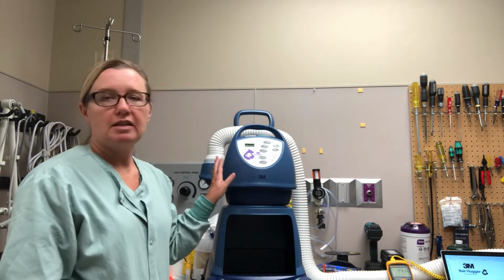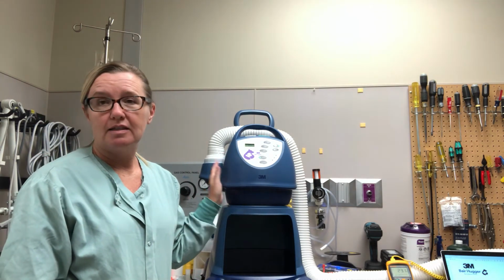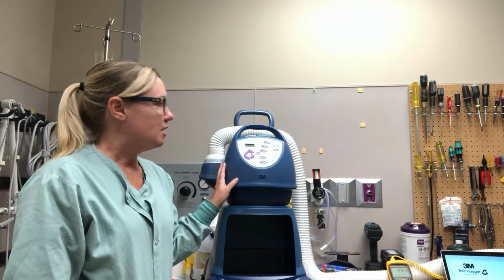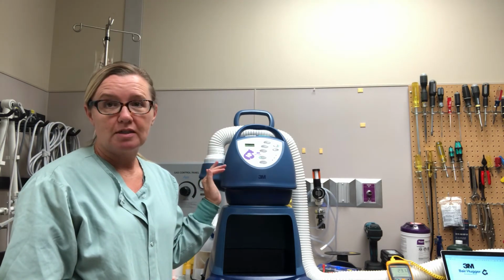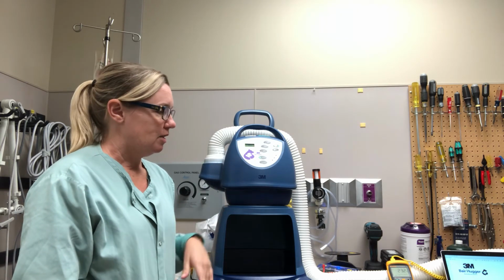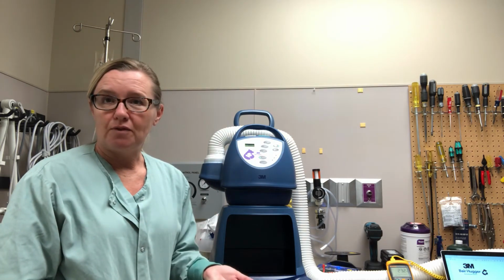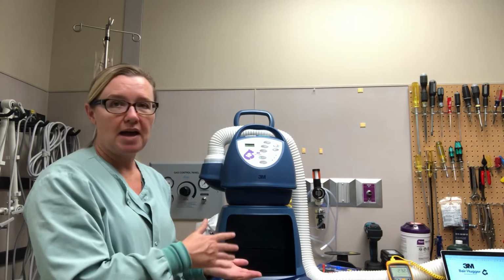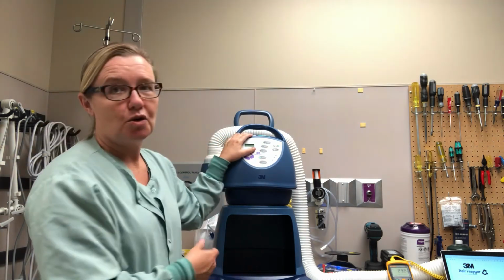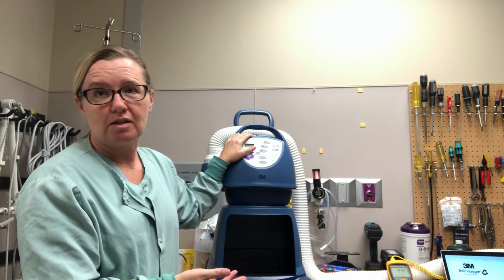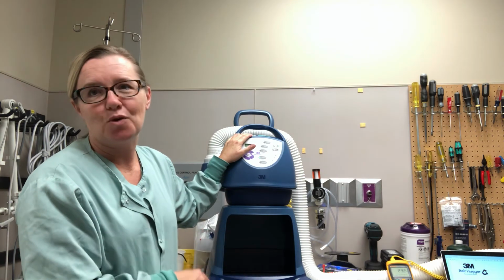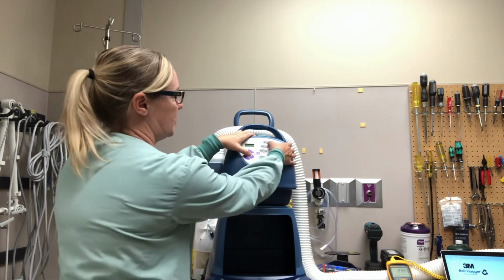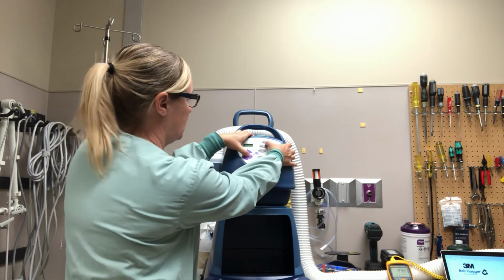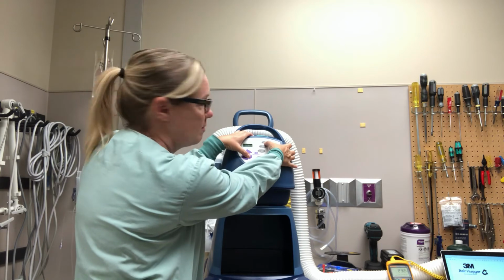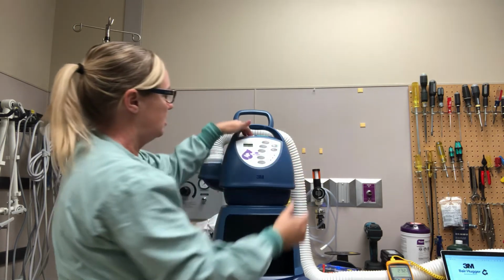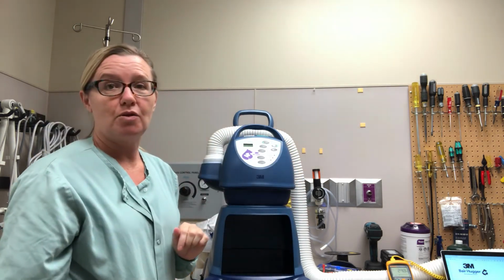Next, we're going to let this run for 5 minutes and stabilize again, and then we'll do our over temperature test. So set the timer, wait for 5 minutes, come back, and we're going to go into the over temp calibration. It's really an over temp test mode. So it's the Bair and 43 degrees. We're going to press both of those and hold them. And now we're in over temp test mode.